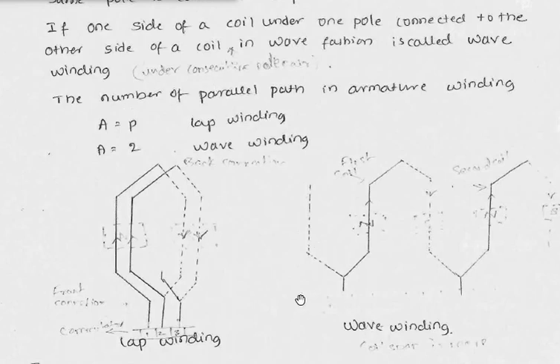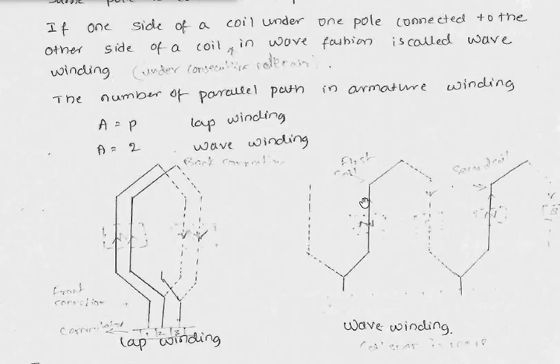In case of wave winding, there is a set of commutator segments. This is the first coil and this is the second coil. If one side of a coil under one pole is connected to the other side of a coil in a wave fashion — one coil is connected to the next coil in a wave fashion — it is called wave winding. If we have wave winding, the number of parallel paths A equals 2. So lap winding gives A equal to P, and wave winding gives A equal to 2.